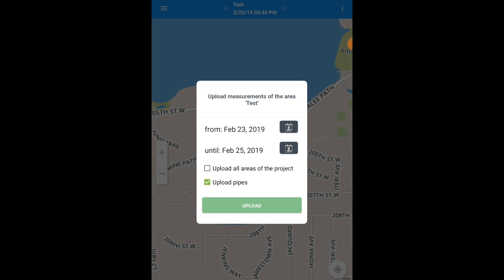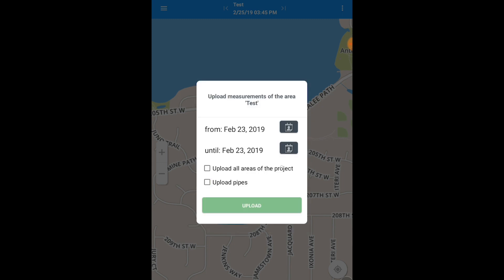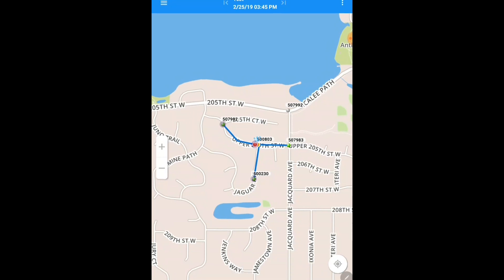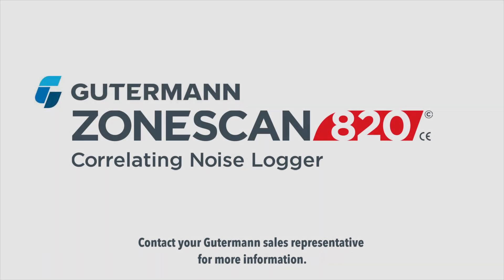In this situation, the loggers listened from 2 to 4 a.m. on the 23rd of February and were retrieved on February 23rd during the day. Edit the date range to reflect when the loggers listened. Make sure that the upload all areas of project and upload pipe boxes are both unchecked. Make sure that your Wi-Fi is currently connected to your tablet and hit upload project. Once the measurements have been sent successfully, it will say 'Gutermann Cloud upload successful' on the bottom of your screen. Congratulations — you have sent your measurements from your deployment of loggers to zonescan.net. Log in to zonescan.net on any web browser to manipulate your leak data. You are now safe to turn off your tablet and store your Gutermann ZoneScan 820 equipment.